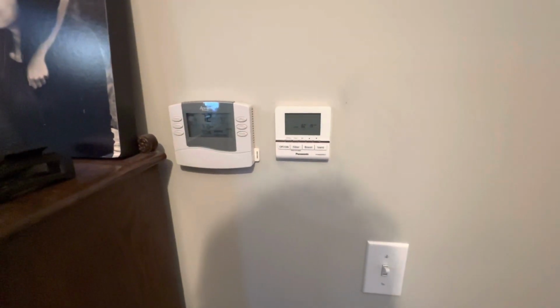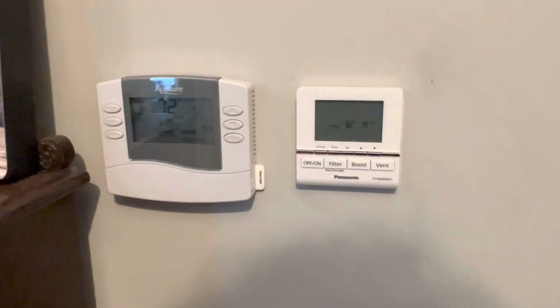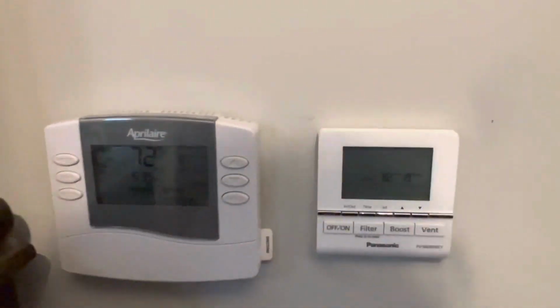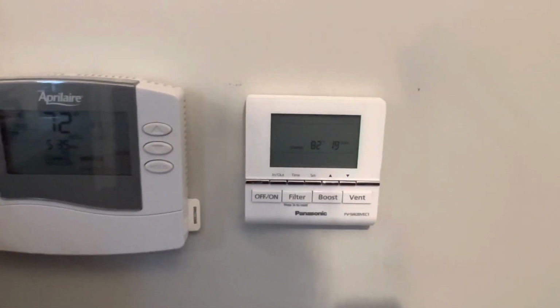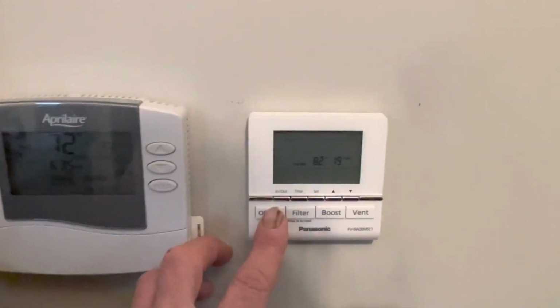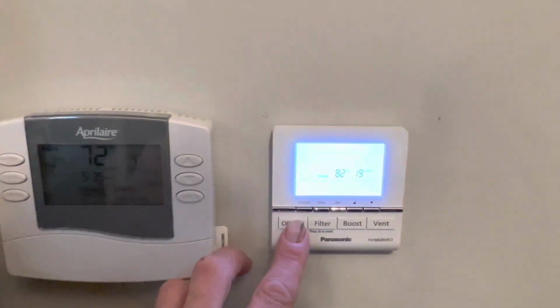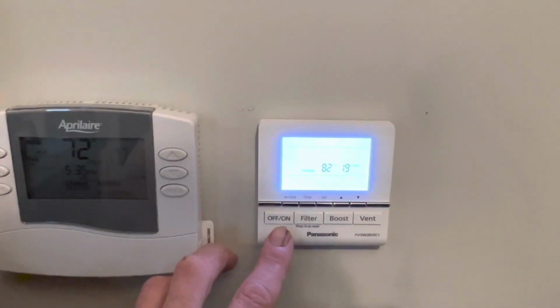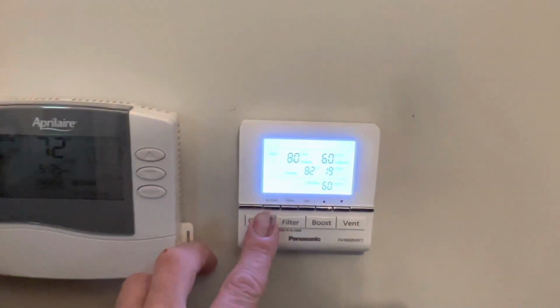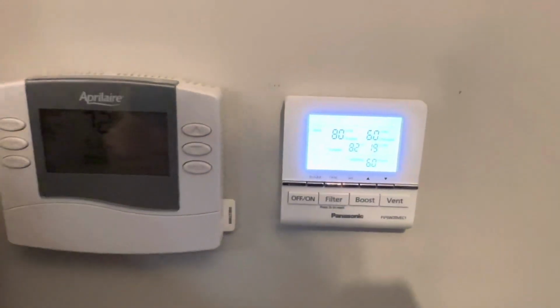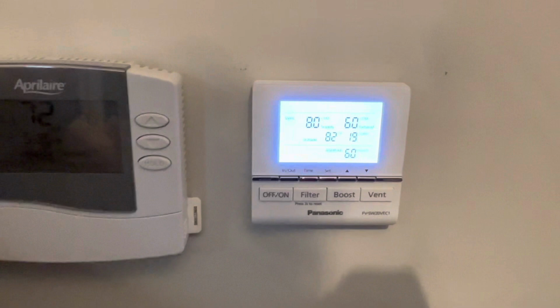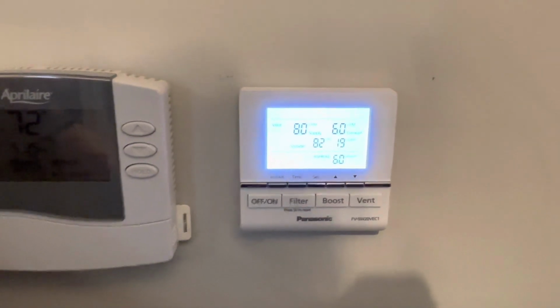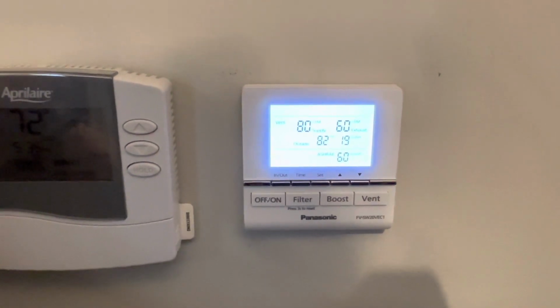So back upstairs at the wall controller. It's off right now. Like I said, when I open that door, it automatically shuts off and won't turn back on until you turn this on with the on button. So that just lit up the display. Push it again. It's turned on. Like I said, that's what I have it set at right now: 80 CFM for supply, 60 for exhaust.